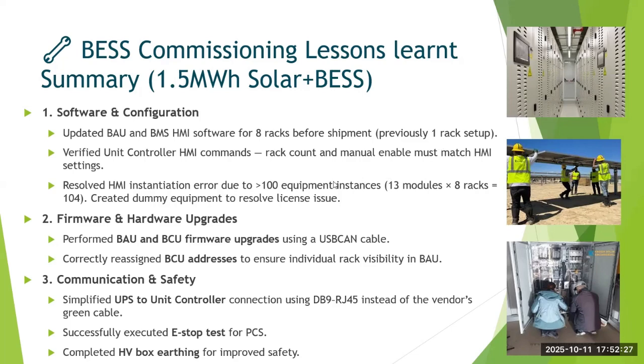And with the HMI, an installation error was coming because the equipment count was more than 100, because they had inherited the HMI installation they had. What they installed had less than 100 equipments, and the license was for that. Now when I went to install the latest software, it was not allowing because this site had 8 racks with 13 modules. In total, it was coming as 104 instances. So it was not happening. Again, a license issue. So again, I had to talk to the BMS vendor and ensure that the licenses are actual licenses in line with whatever we asked for.